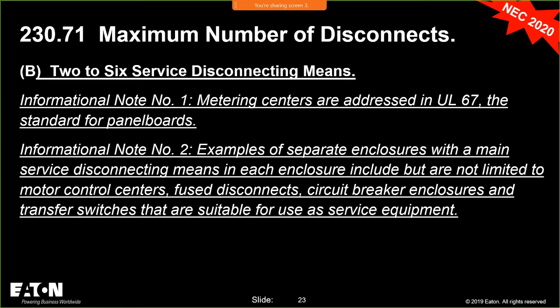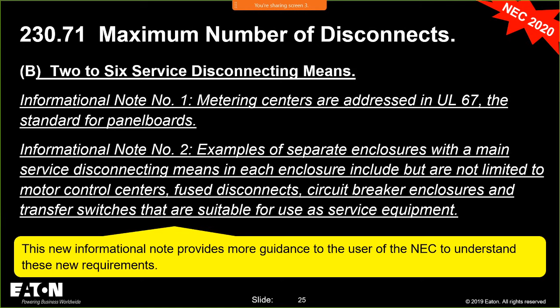Examples of separate enclosures with a main service disconnecting means in each enclosure include motor control centers that have a main, fusible disconnects, circuit breakers, enclosures, etc. This is a big change for the National Electrical Code, and we're changing the six disconnect rule, which has been in place since the 70s without much change. There's a lot of things being looked at that we've lived with for many years, and they're asking the right questions and taking the right steps to increase electrical safety. So the six disconnect rule changed in a manner to increase safety, focused on the electrical worker.